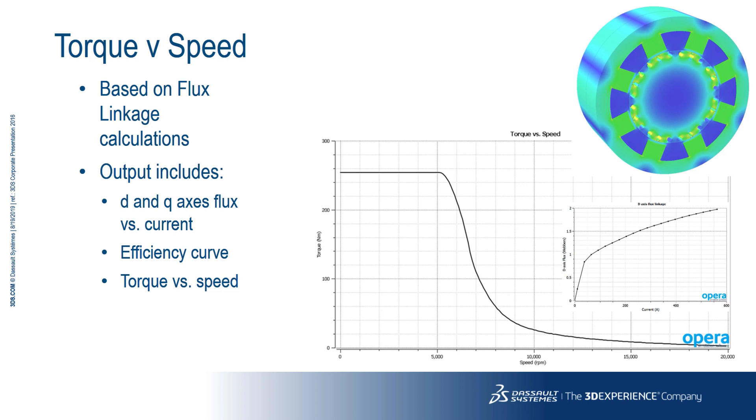The torque versus speed analysis provides a quick way of evaluating the torque speed characteristics based on flux linkage calculations. The output includes d and q axis flux versus current, efficiency curve and also torque versus speed.